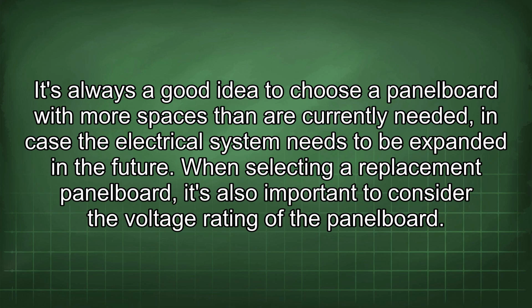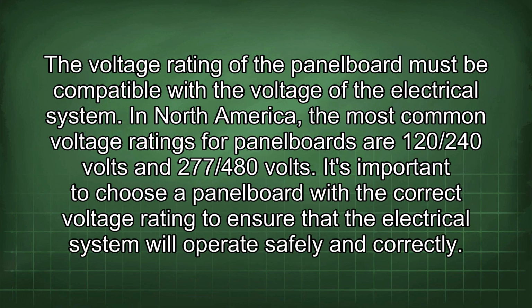When selecting a replacement panel board, it's also important to consider the voltage rating of the panel board. The voltage rating of the panel board must be compatible with the voltage of the electrical system. In North America, the most common voltage ratings for panel boards are 120/240 volts and 277/480 volts. It's important to choose a panel board with the correct voltage rating to ensure that the electrical system will operate safely and correctly.